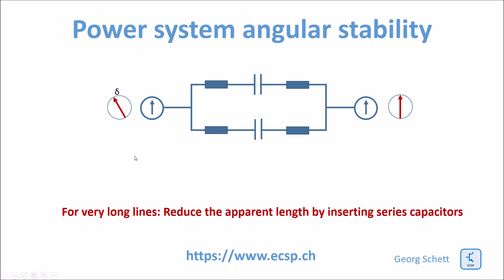So if you add series capacitors to the system, you will see that you decrease the phase angle between the sending and the receiving end. So this is without capacitors. Observe the phase angle. And this is with capacitors. So here you can clearly see the impact such series capacitors have.